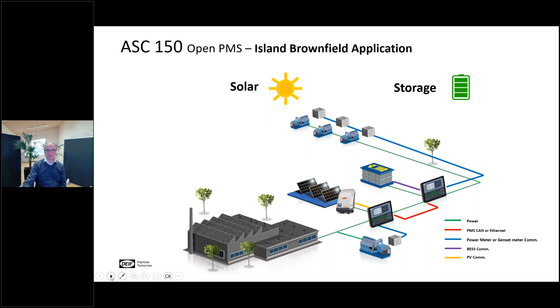You can actually do what is easier for you. So if this generator is down here, you can connect it to the first controller, and if these generators sit up here, you can connect them to the second controller. The communication between the controllers will be done via a power management link, an internal power management - either CAN bus, which is what we've traditionally been using, but we also offer the possibility to do power management over Ethernet on these AGC ASC 150 devices.